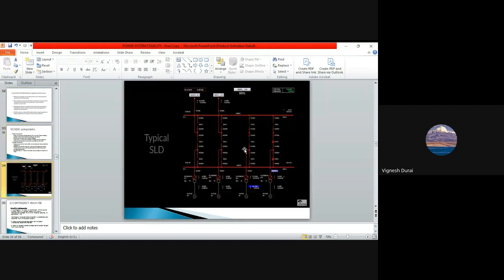In real time, our SCADA system will show a display like this. Suppose this is the generation station. You can see these are all your buses. This is your 400 kV bus, and these are our switches, and you will see breakers here. You can see a breaker here. See this graph, these are analog values and digital values. Everything, whether it is on or off or your analog value in the field level, will be seen by our load dispatch centers in control centers. You can watch this screen like this.